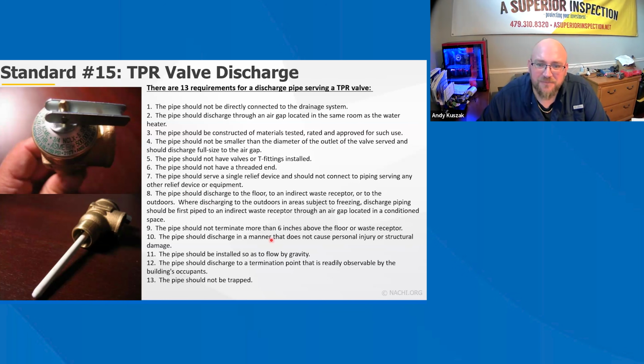The pipe should discharge in a manner that does not cause personal injury or structural damage. That structural damage goes back to the temperature pressure relief valves. It's very common, and they still do it in new construction today, where they terminate the TPR valve in the crawl space. So in the wintertime, say you have all your crawl space vents blocked off, so there's no airflow. Your TPR valve is terminating in the crawl space. You just created a sauna for your wood structure.